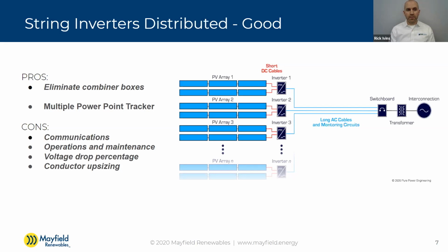Of course, if you don't have that combiner box and you're going straight into the inverter, odds are that inverter also has multiple power point trackers, whether it's 3 or 6 or more. When you have a combiner box, you're probably going in with a single feed, all the strings on a single power point tracker. When you're going right into the inverter, you're likely using the multiple power point tracker options. That's really beneficial for in-row shading, shade from trees, or debris like leaves that fall on the panels. The power point trackers help isolate those mismatch losses to just a string or two and don't affect the other strings on other MPPTs. So you might be able to squeeze out a tiny bit more energy from your system by having those multiple MPPTs in use.